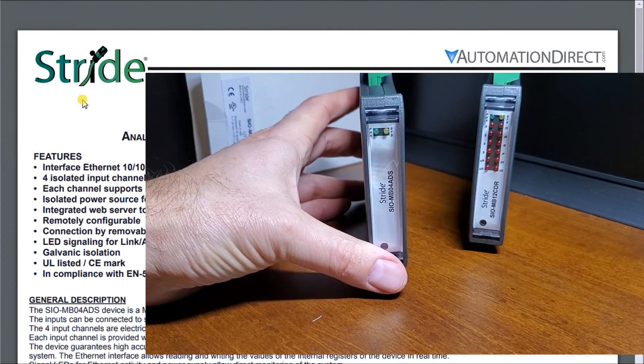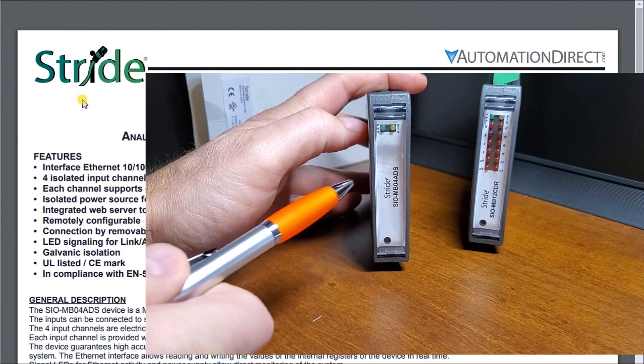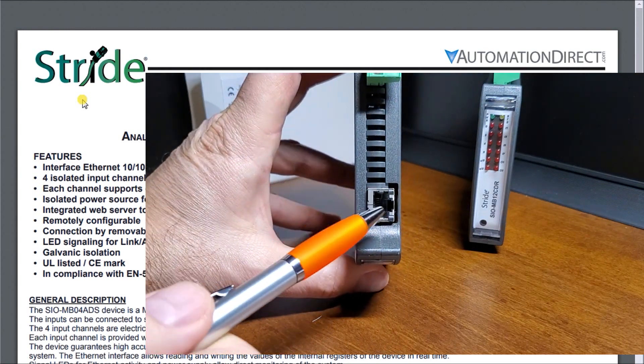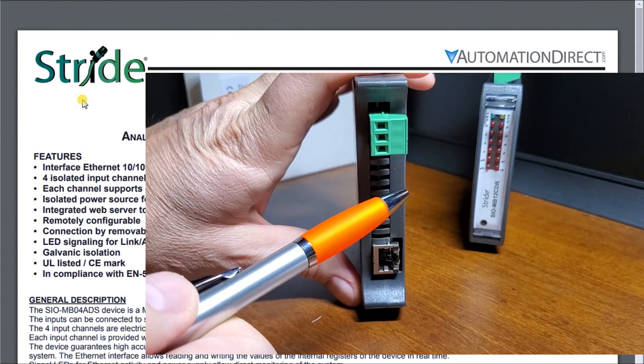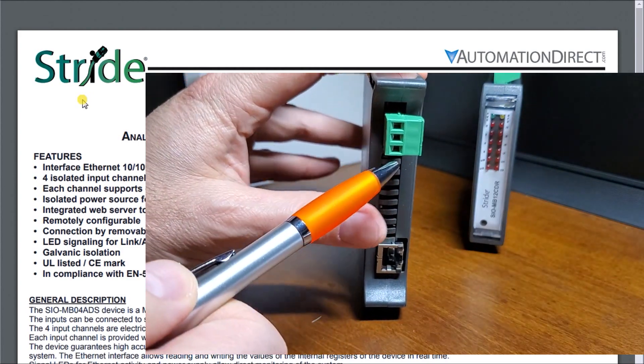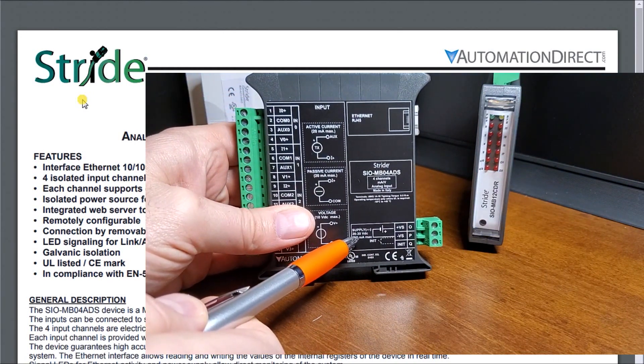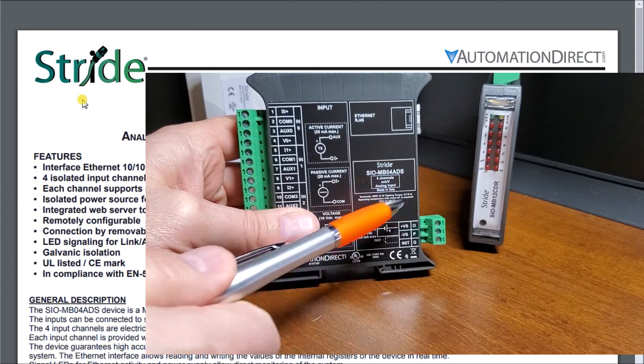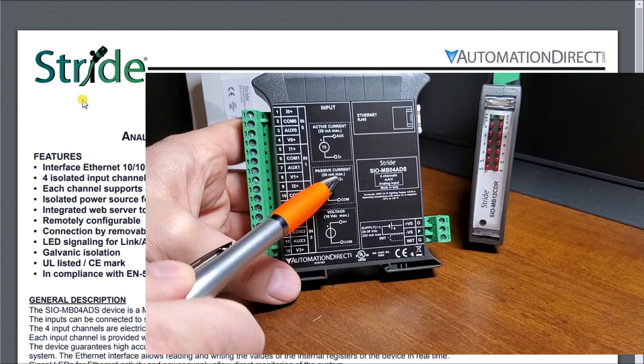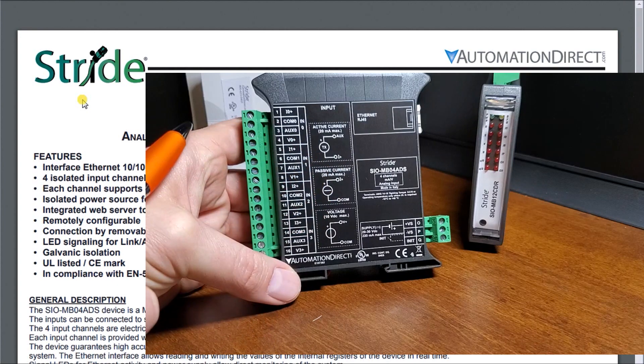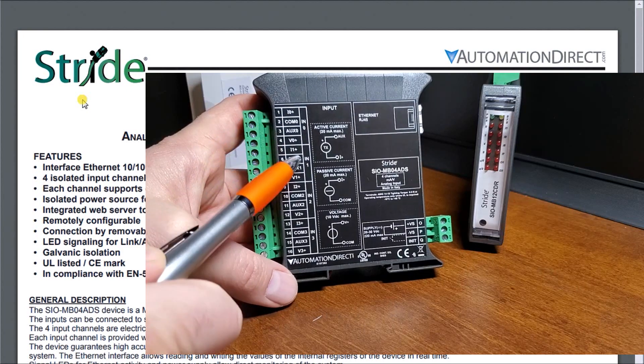Looking at the actual hardware itself, you can see we have our reset button, and our power and status lights here. On the top we have our Ethernet connection and our supply voltage input. Looking at the back, the supply voltage is anywhere from 20 to 30 volts DC — that applies to both units. Then we have our current connections — passive and active — our voltage connection, and our inputs: channels one, two, three, and four listed on the side.